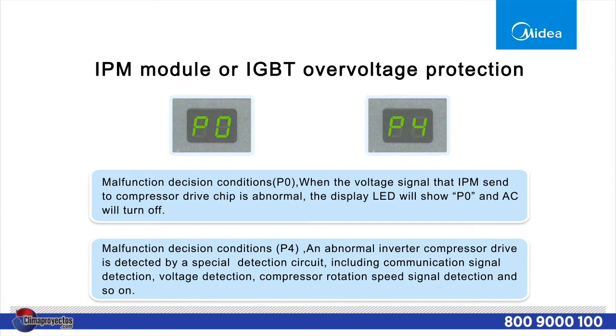Malfunction Decision Conditions, P4: An abnormal inverter compressor drive is detected by a special detection circuit, including communication signal detection, voltage detection, compressor rotation speed signal detection, and so on.